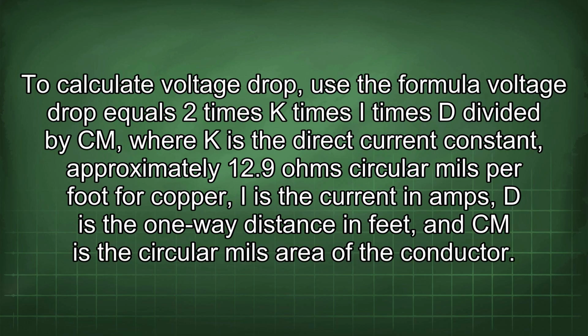To calculate voltage drop, use the formula: voltage drop equals 2 times K times I times D divided by Cm, where K is the direct current constant, approximately 12.9 ohms circular mils per foot for copper, I is the current in amps, D is the one-way distance in feet, and Cm is the circular mils area of the conductor.